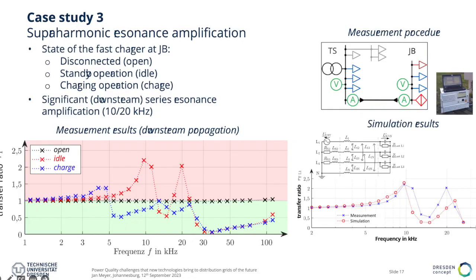They asked us to investigate that a little and find the explanation. What we did was basically a propagation measurement: we used a generator that could produce a variable frequency, injected it at that point at the transformer station, and measured at the same time at the transformer station and the junction box, so we could really see this amplification characteristic.